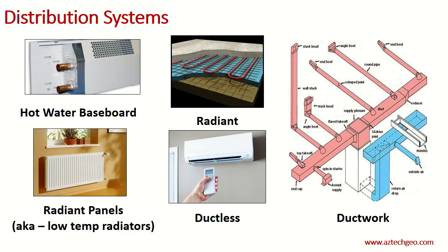Under the subfloor is not that friendly, so staple-up kinds of systems are less friendly to heat pump systems because we don't have the output, or we end up running in a less efficient, higher temperature mode. That's also true for combustion systems. If I have a condensing boiler, I'm not condensing in that boiler if I'm anything above 140 degrees anyway, and I'm starting to fall on a hairy edge.